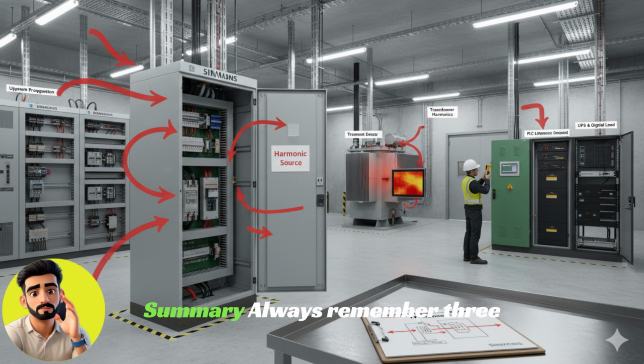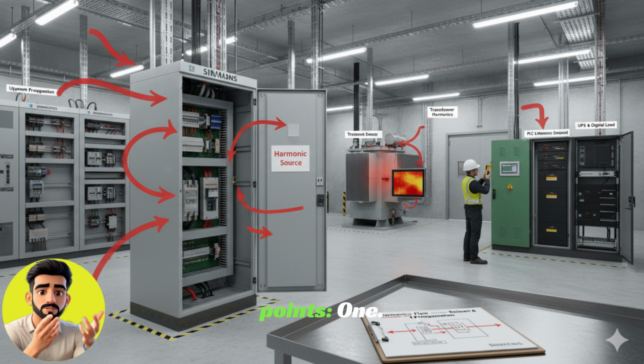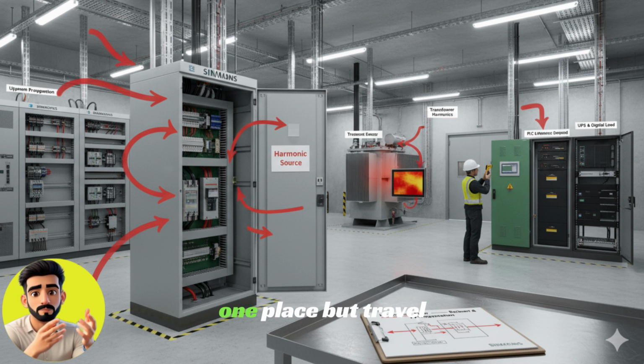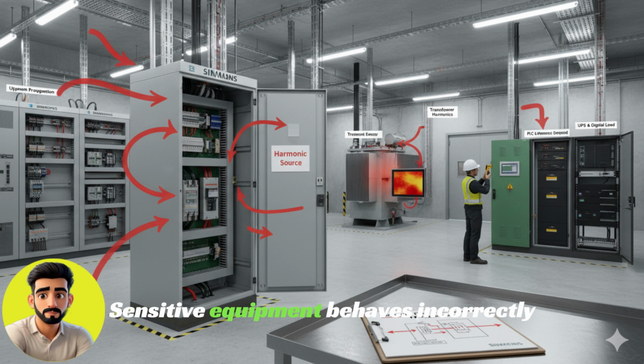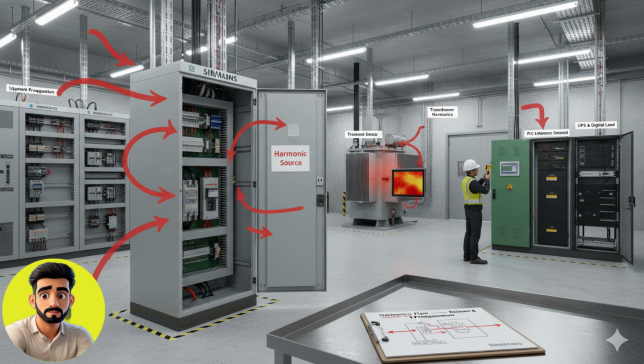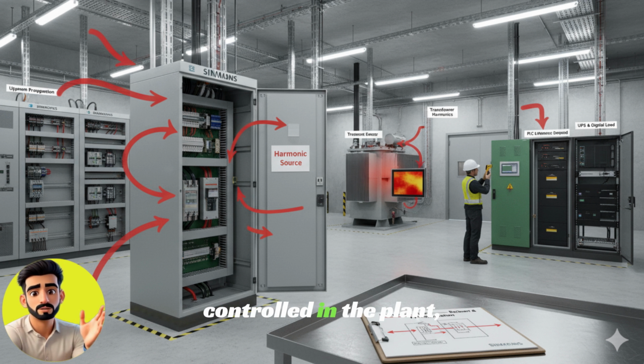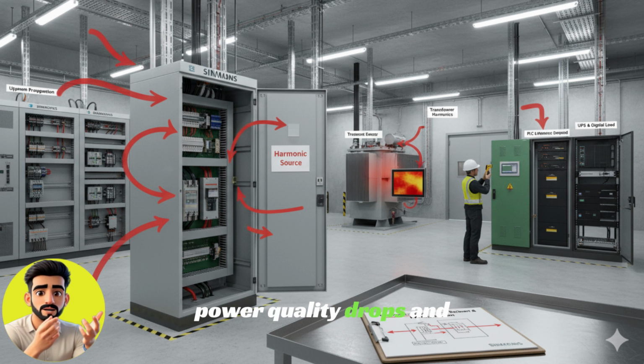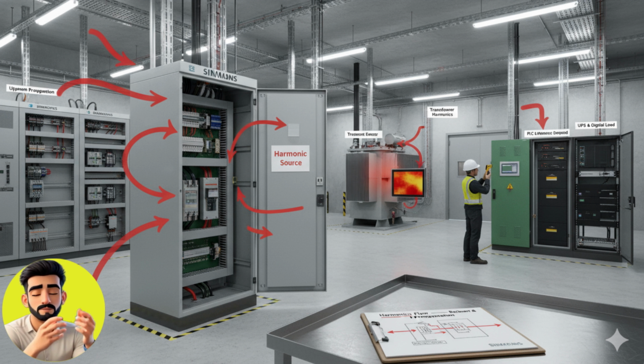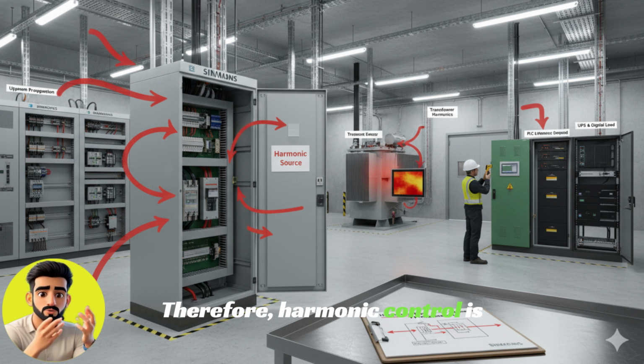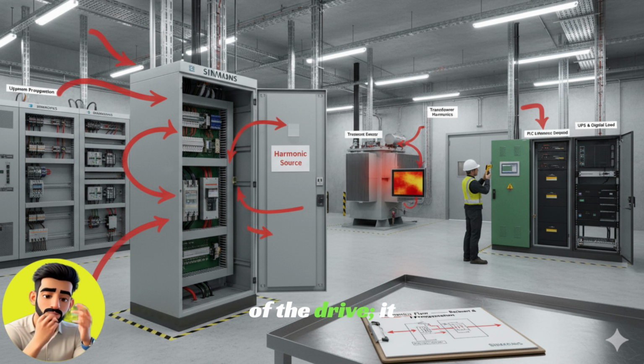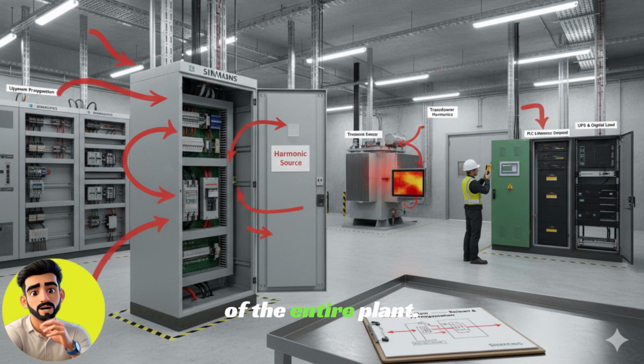Summary. Always remember 3 points. 1. Harmonics are generated in one place but travel throughout the plant. 2. Sensitive equipment behaves incorrectly with harmonics. 3. If harmonics are not controlled in the plant, power quality drops and reliability decreases. Therefore, harmonic control is not just an issue of the drive, it is a health check of the entire plant.